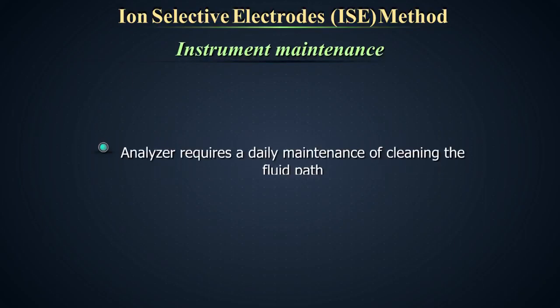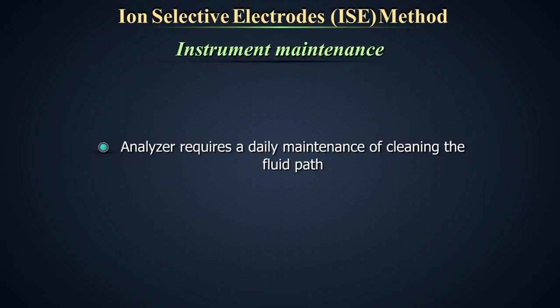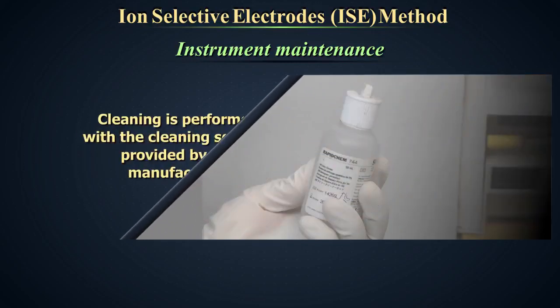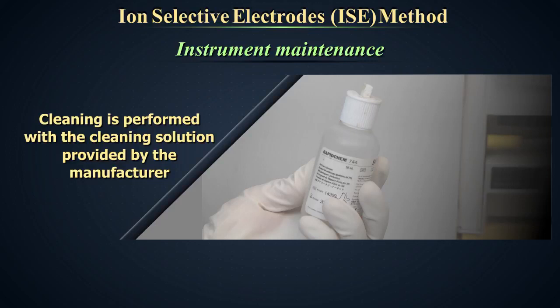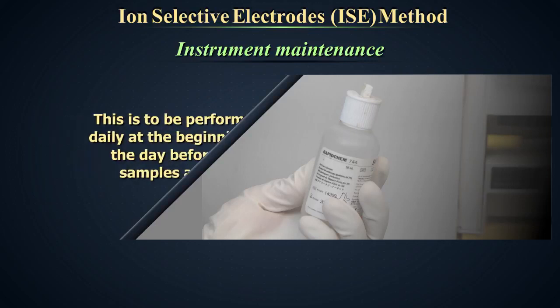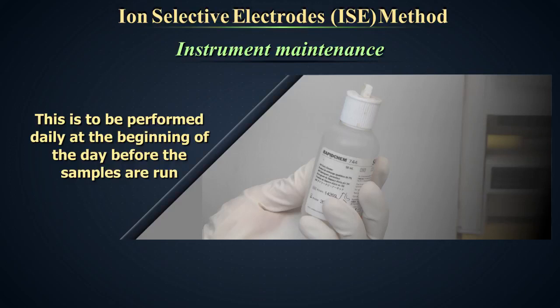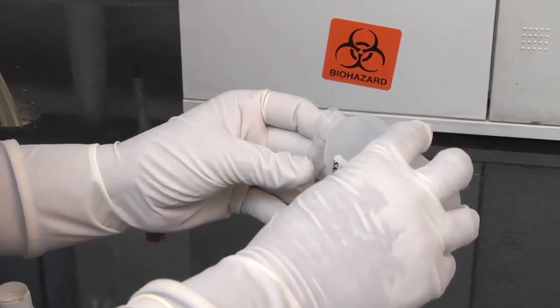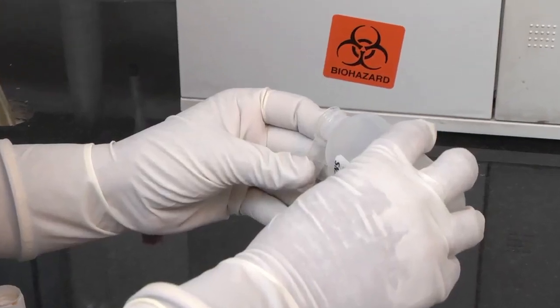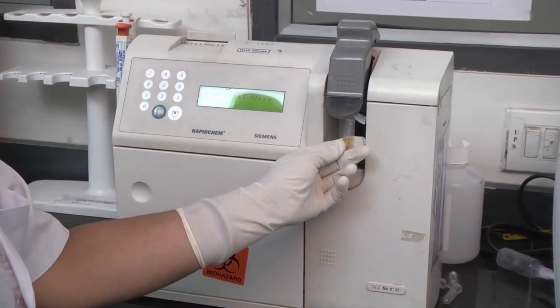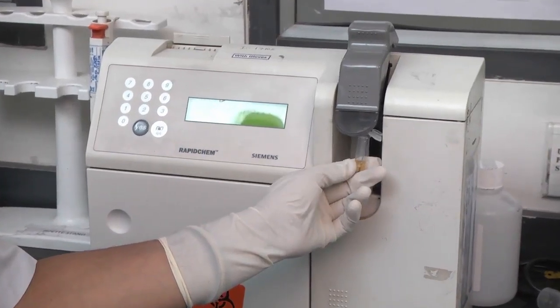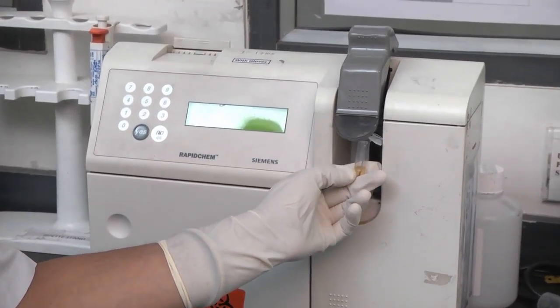Instrument maintenance. The analyzer requires a daily maintenance of cleaning the fluid path to remove protein deposits. Cleaning is performed with the cleaning solution provided by the manufacturer. This is to be performed daily at the beginning of the day before the samples are run. Take the cleaning solution in a clean container to avoid contamination of the remaining solution. Run the cleaning solution like a sample, but in the daily cleaner mode. The cleaning cycle will be completed in 75 seconds.